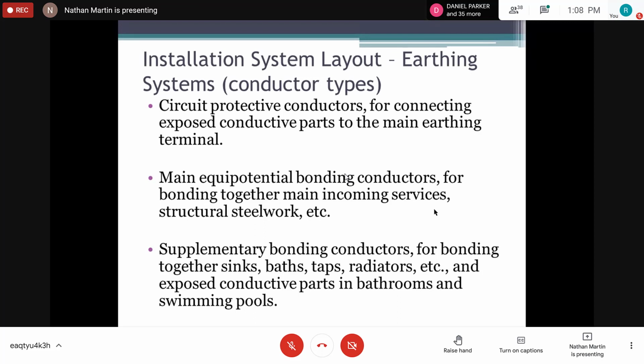However, for most applications, for instance, you're using a twin and earth cable. You might be using a 2.5 twin and earth cable. What you realize is that if you look at the specifications of the cable, the two phase conductors would be 2.5 and the earth conductor will be 1.5, right? So that is saying that your earth conductor can be one size less than your phase conductors. But just to be safe when we are doing our installation, we normally select the earth conductor to be of similar size as the phase conductor. And that is when we are using single core cables, all right? That's when we're using single phase cables.